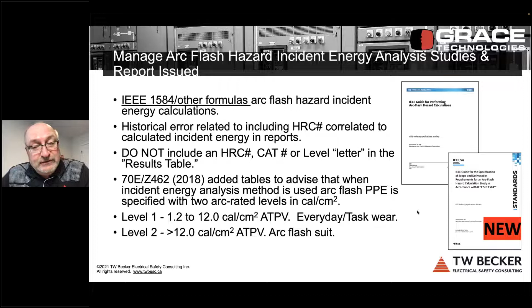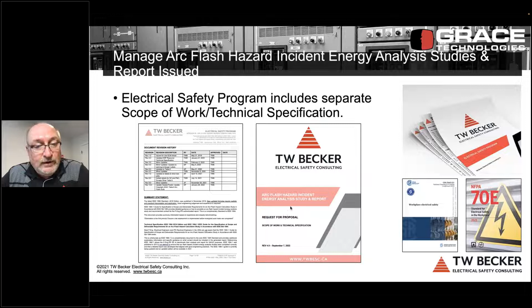You can't just say in your RFP, you must comply with IEEE 1584.1. If you at least say that, that'll be better than just saying, give me an arc flash study, because you can audit the consultant against 1584.1. But what I recommend is that you have your own company arc flash incident energy analysis study and report, and it'll have additional information for pre-qualification of the consultant, a lot more detail there, and then following the procedural steps in 1584.1, and then actually offering a compliant label.